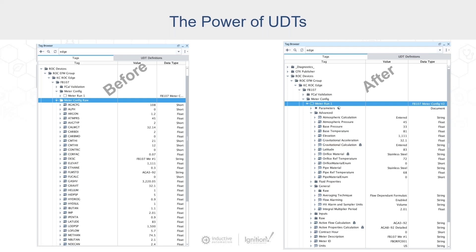What we show here is taking all of that information and, by using an Ignition UDT on the right side, you can see that we've got our UNS here. This is my ROC EFM group and I'm at my Kansas City ROC edge. There happens to be a FloBoss 107 there. Under that, I've got the meter configuration, highlighted in blue — a FloBoss 107 meter config V2. I took these tags and mapped them into a UDT structure. Now I've got a folder called 'advanced' with humanly understandable tag names assigned to those process variables coming out of the flow computer.